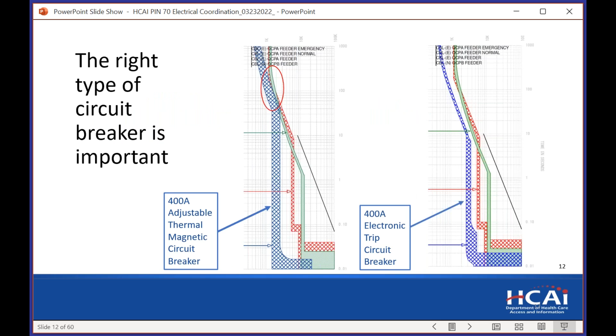Bill, I think this question might have been referring to faults that trip before a tenth of a second. If it's the tenth of a second, this is understanding that most faults are not bolted faults where you're going to have your full available fault current. And so this is a compromise that came up with NFPA 99 to not require full coordination, because full coordination of an essential electrical system used in a hospital would be a challenging feat with how complicated our systems are. And so this is a compromise of true coordination of breakers.